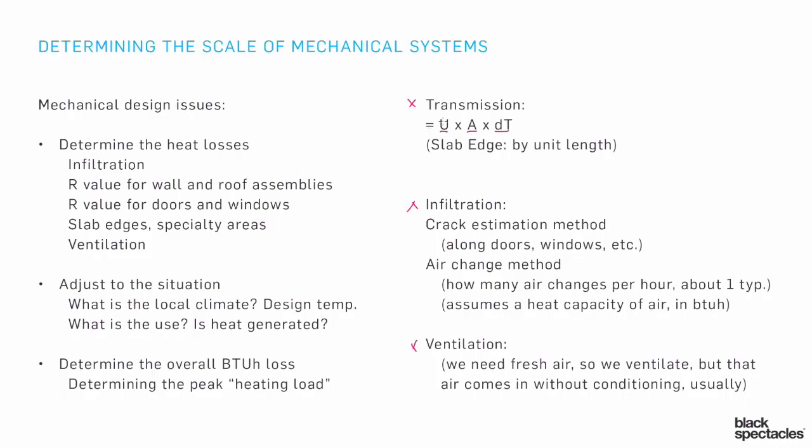That tells us we need to be putting a lot of heat energy into the heating system in order to balance out the loss of heat through transmission — through the roof assembly, through the wall assembly, etc. The U, remember, is the same as 1 over the R. It's the inverse of the R value.